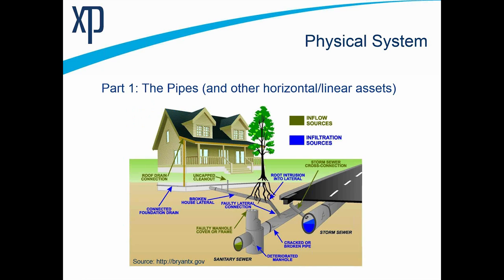First up is pipes and the other horizontal or linear assets. In this example you can see a true separated system — you can see the storm sewer system. We're going to avoid the stormwater side and stay strictly in the sanitary side. Some of you may have combined sewers, but since that's a different set of issues, we'll talk just about the separate sanitary sewer. You can also see cracks in the pipe, which is more of the main line that usually runs parallel to a road. You can see the clean out and the lateral — this is showing a pretty broken connection having been in the ground for some amount of time.